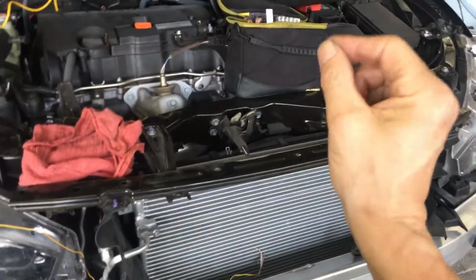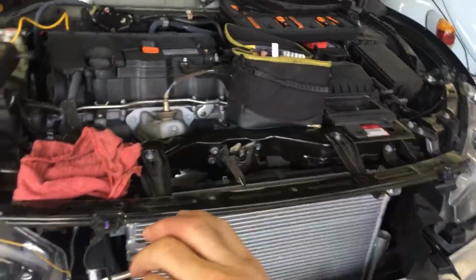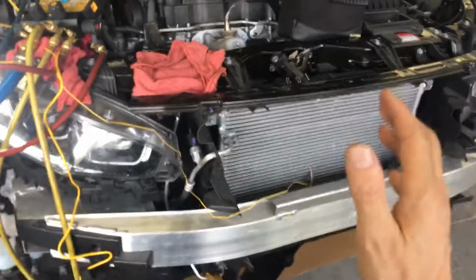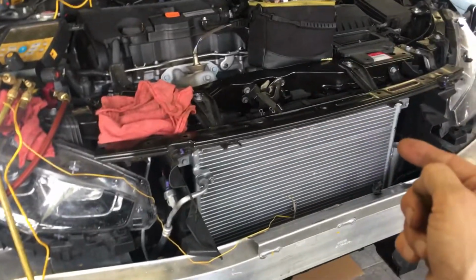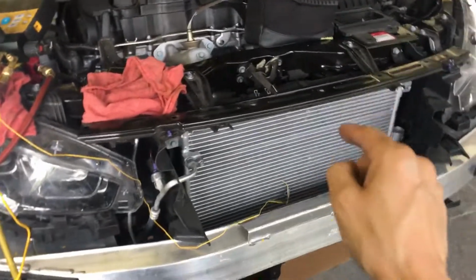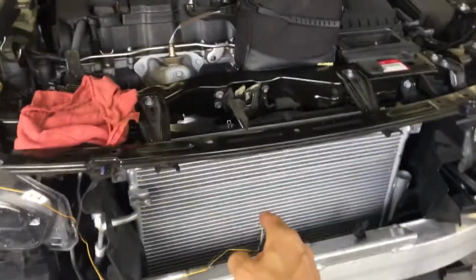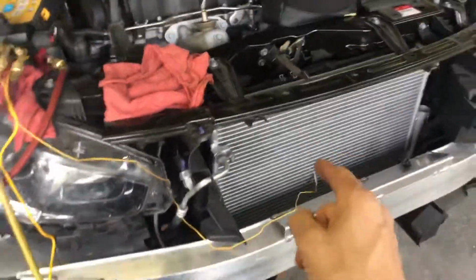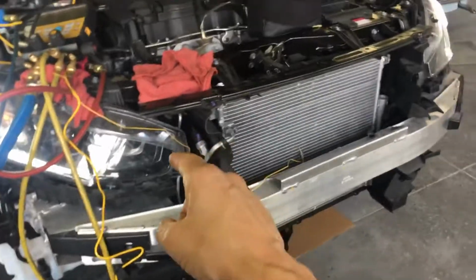Up to a certain point, your high side will be okay, your cooling will be okay. Once you hit that - the straw that breaks the camel's back kind of thing - you got that nuclear meltdown, that runaway, thermal runaway, let's explain it like that. You pass this peak threshold, and on that day, at that temperature, is when this aftermarket condenser stops giving good cooling and gives you a massively high side.